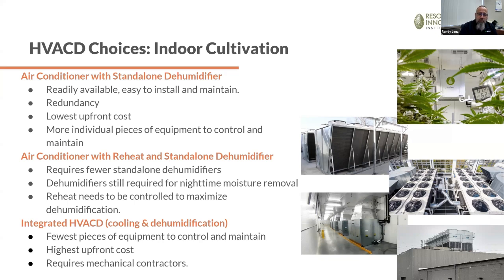With reheat systems, it's pretty much the same, just a bit more complicated on the air conditioning control side. You have to make sure the control logic keeps that air conditioner running and rejecting the right amount of heat, so you maintain your cooling set point and offset some dehumidifier load. You still use standalone dehumidifiers at night, but fewer of them. The integrated system has the fewest pieces but the highest cost, and requires mechanical contractors to operate and maintain it. But it's good equipment designed to remove the heating load, cooling load, and moisture load together in one packaged unit.